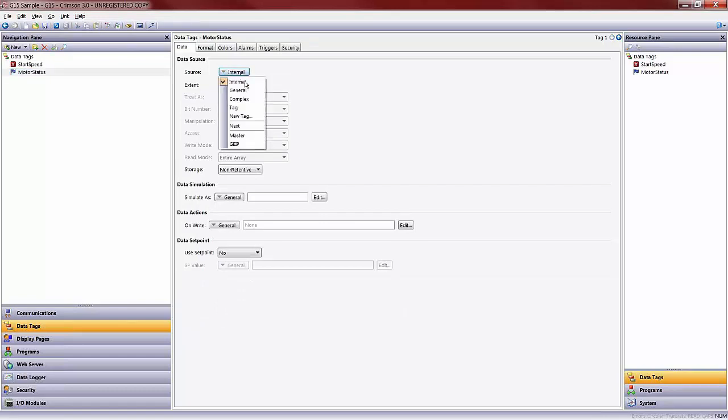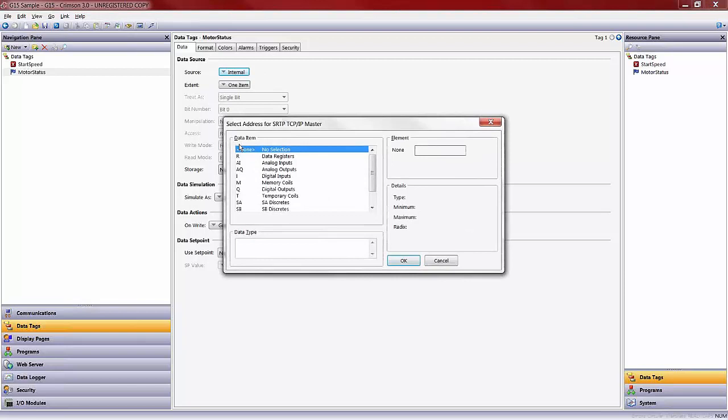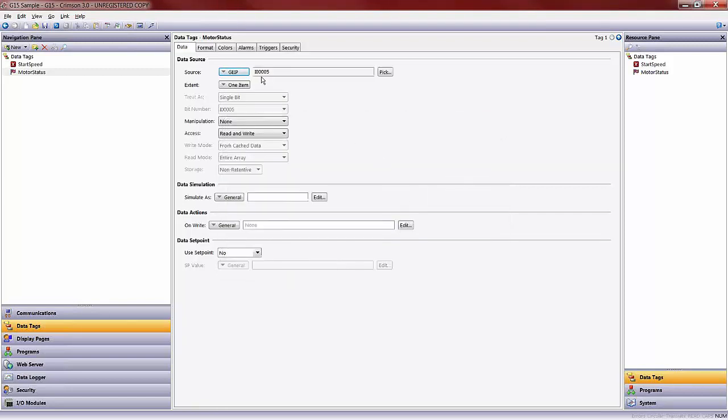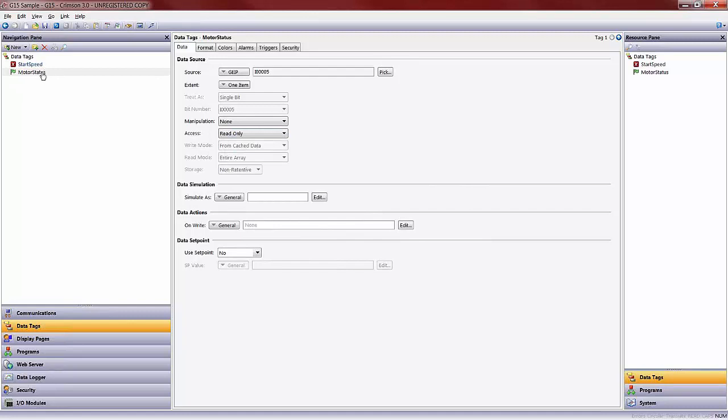The motor status then, I could come over and map through the same process. For example, to a digital input, a percent I. In this case, let's say it's percent I, 5. Notice that I do not have to put in the zeros for after. It will automatically add for me. Right there. I am going to change the access here to read only, because it is just going to be status, nothing that I want to feed back. You now have two tags that are mapped to a GE IP controller.